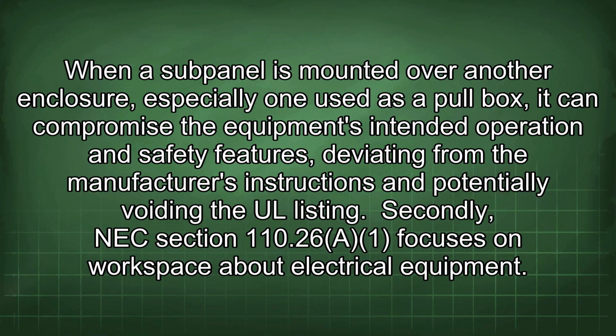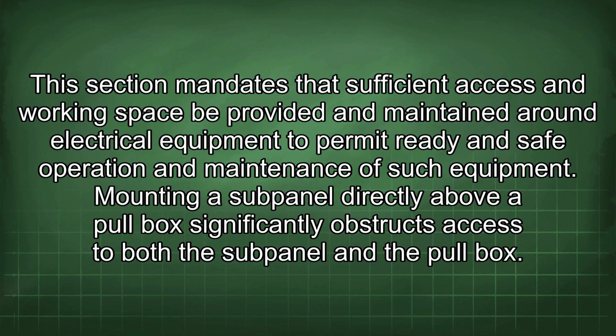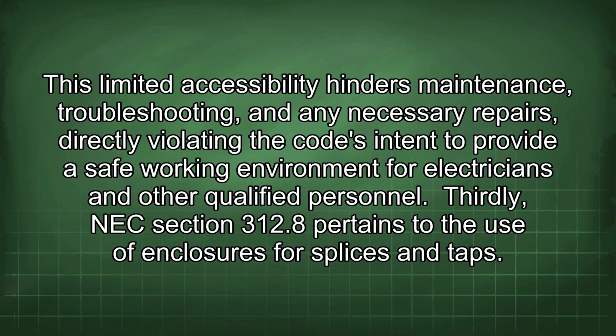Secondly, NEC Section 110.26(A) focuses on workspace about electrical equipment. This section mandates that sufficient access and working space be provided and maintained around electrical equipment to permit ready and safe operation and maintenance of such equipment. Mounting a subpanel directly above a pull box significantly obstructs access to both the subpanel and the pull box. This limited accessibility hinders maintenance, troubleshooting, and any necessary repairs, directly violating the code's intent to provide a safe working environment for electricians and other qualified personnel.